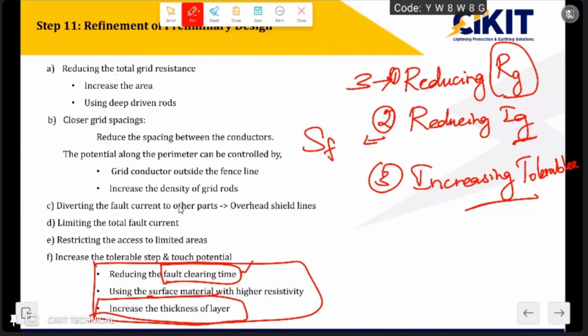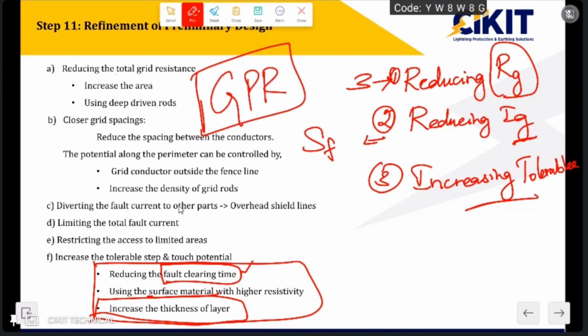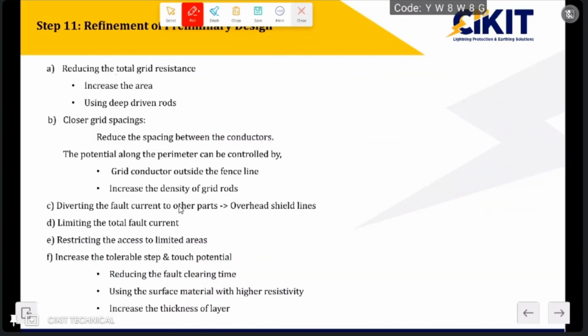So in all these steps, around 12 steps, if you closely observe, nowhere have we considered the grid resistance value. The grid resistance value is considered only for the GPR. It is not considered for ensuring the safety of the person, or for ensuring whether the design is safe or not. So the value of Rg is maintained only to keep the GPR in control. So Rg is not the deciding parameter. The deciding parameters in an earth mat system are the step and touch voltages.